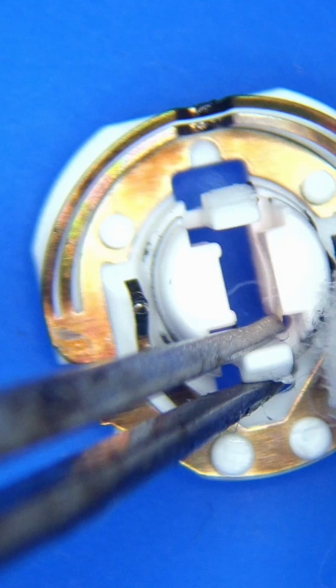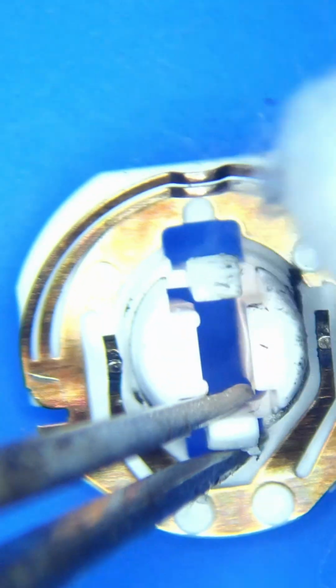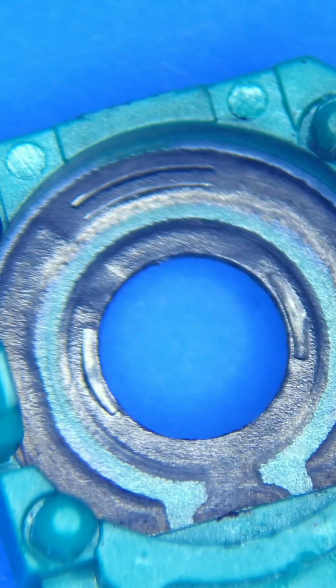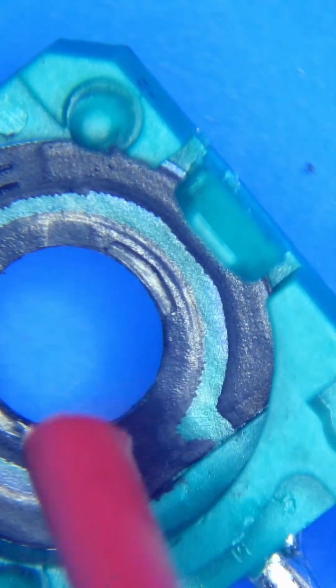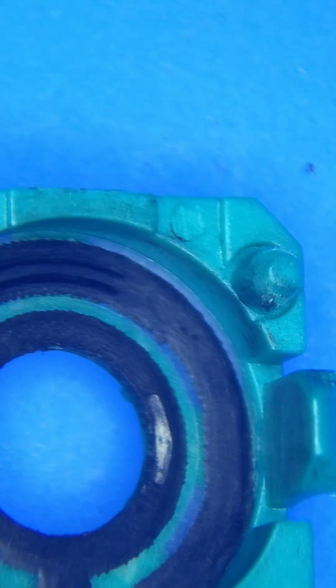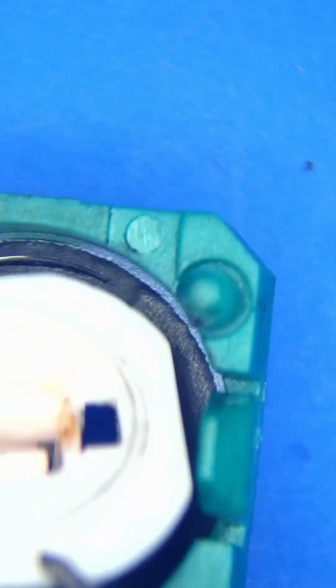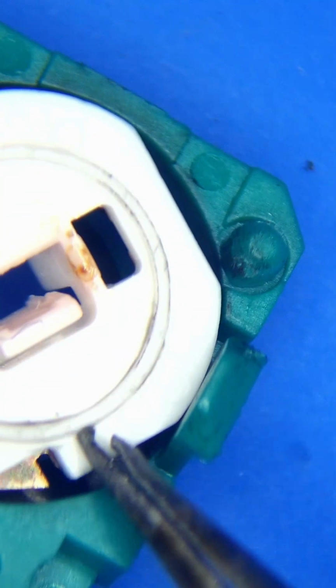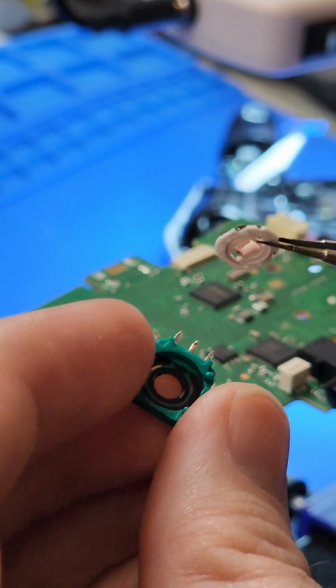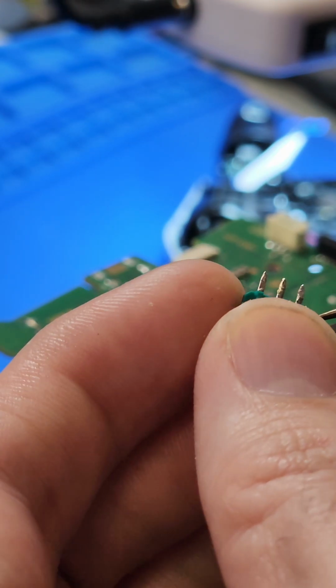Now let's take a look at the brush. As I brush away the carbon built up on the sensor, notice the metal brushes have a shiny flat spot, especially on the center brush, which is the voltage range. The top brush is the sensor range that determines the positioning of the stick. The voltage in the center has some serious metal fragments, and at the very top sensor, where the two lines are, that's where you get the voltage change as the brush moves back and forth for calibration, ranging between about 1.8 volts and less than a volt as it goes up and down.